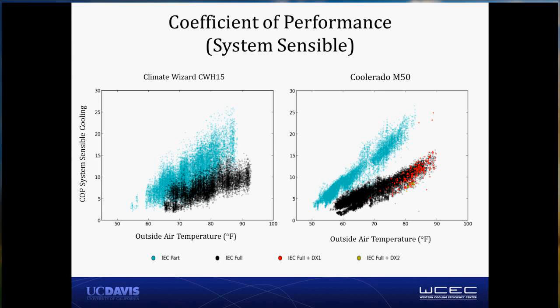I think I failed to describe that the way this equipment is installed on the store is so that when operating at part speed, which was about 75% airflow rate, these 6 units operating in parallel provide for the entire 12,000 CFM of required continuous ventilation for the sales floor. And when there's an additional call for cooling from the store, the equipment ramps up to full speed, 100% airflow and an increased capacity.